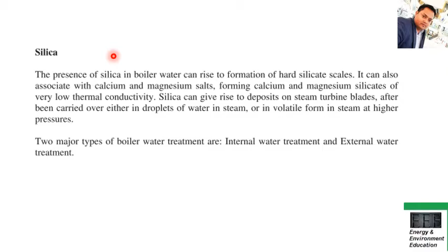So basically, you need to understand that there should be less presence of silica in the boiler water. The water you are feeding inside the boiler should have less silica, otherwise it will lead to silicate scale formation, and this will really hamper the boiler efficiency, which will be lowered, and also the performance of the boiler will be low in that case, friends. So silica can give rise to deposits on steam turbine blades. This is also a drawback: if you are generating steam and running the turbine, the turbine blades will have more silica deposits, after being carried over either in droplets of water and steam or in volatile form at higher pressures, and this will lead to low efficiency of the turbine also, friends. So you can see the boiler performance, and the turbine also has lower efficiency or performance once there is silica in the boiler water that you are feeding inside the boiler, friends. So you should have the silica content in the boiler feed water as low as possible.